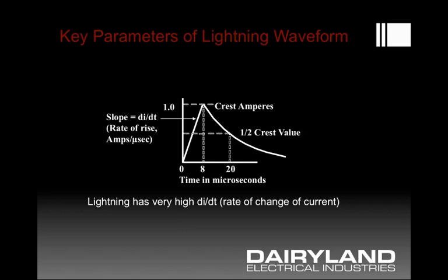Let's talk about lightning. It has very particular characteristics shown here on this graph, where it has a very fast rate of rise of current. The slope of that rising line is extremely fast — we call that dI/dt, or rate of change of current. It goes up to some peak value, which could be various levels from thousands of amps to even up to a couple hundred thousand amps under worse conditions. It rises in a certain rise time, say 8 microseconds, and then decays back down to half of that peak value in 20 microseconds. That example waveform is called an 8 by 20 microsecond waveform. This is an event that happens very quickly, measured in millionths of a second, with a very high rate of rise of current — which becomes an important factor in some of our calculations later.